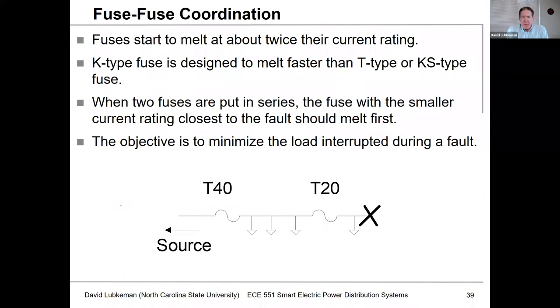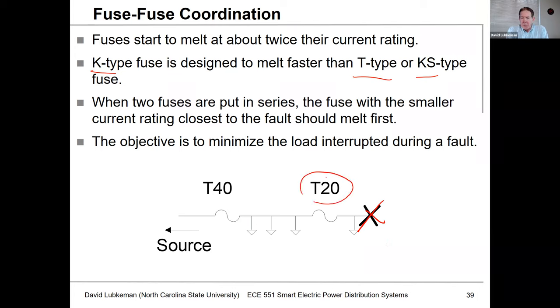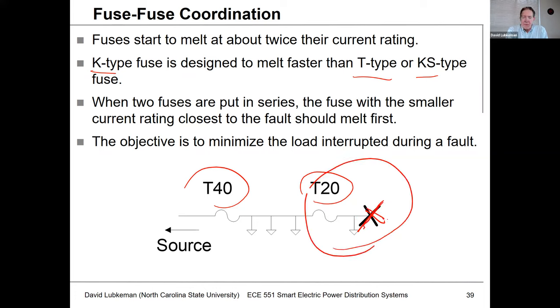Fuse-to-fuse coordination is also possible. Fuses start to melt at twice their current rating. K fuses are the fastest, followed by T and KS types. When coordinating fuses in series — say a T40 upstream and a T20 downstream — for a fault at the far end, the smaller downstream T20 fuse operates first, so upstream customers don't experience an outage. Current levels naturally drop further down the lateral, and with proper coordination, selectivity improves. However, if fuses are very close together, there may not be enough difference in fault current to properly coordinate them.